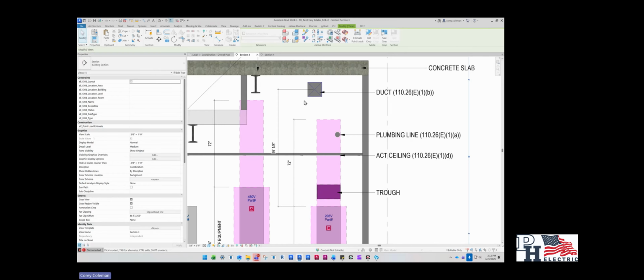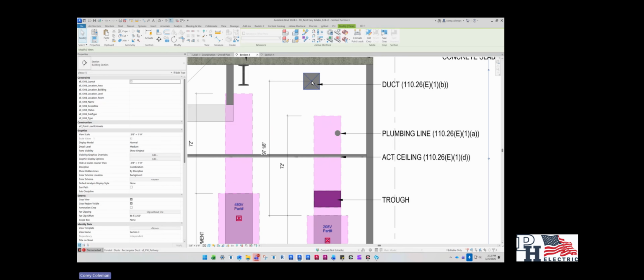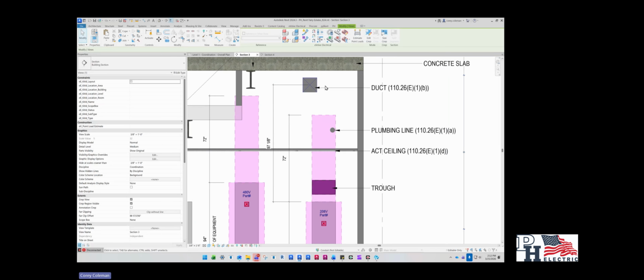We don't know who has to provide it. The inspector usually doesn't want to see a drip pan, because why would a new building need it if we're installing it? If you're in an existing building and there's really no way around it, that's how you can get around code. But more or less, if you're doing a new installation, you want to avoid having your equipment under any other equipment other than electrical.